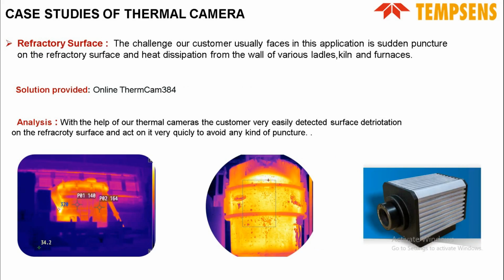Refractory surface. The challenge our customer usually faces in this application is sudden puncture of the refractory surface and heat dissipation from the walls of various ladles, kilns and furnaces. We provide our online ThermalCam 384 model. With the help of our thermal camera, the customer very easily detects surface deterioration on the refractory surface and acts on it very quickly to avoid any kind of puncture in that surface.